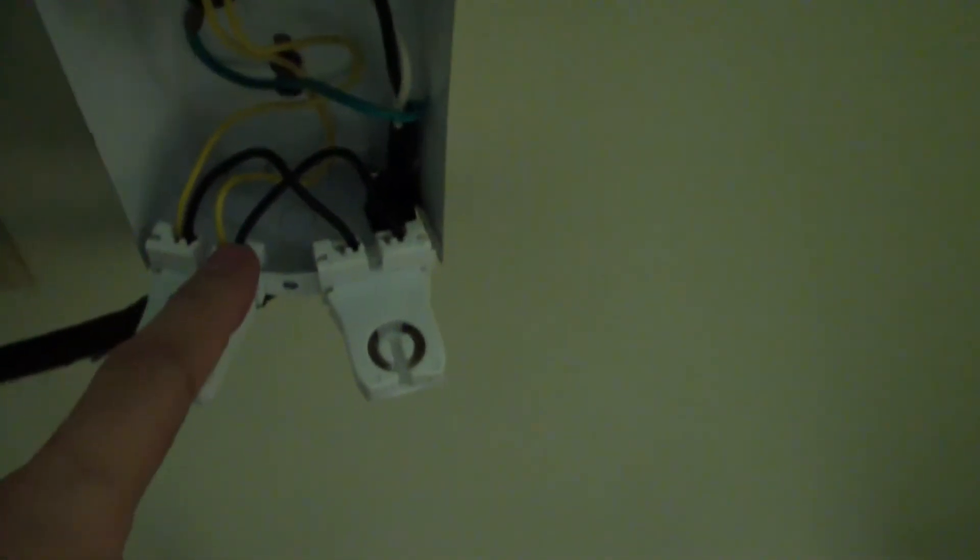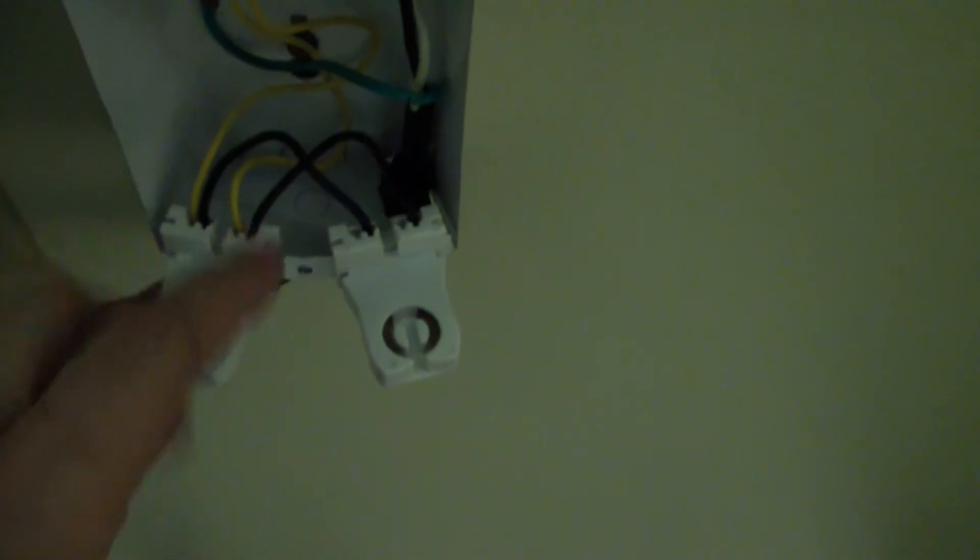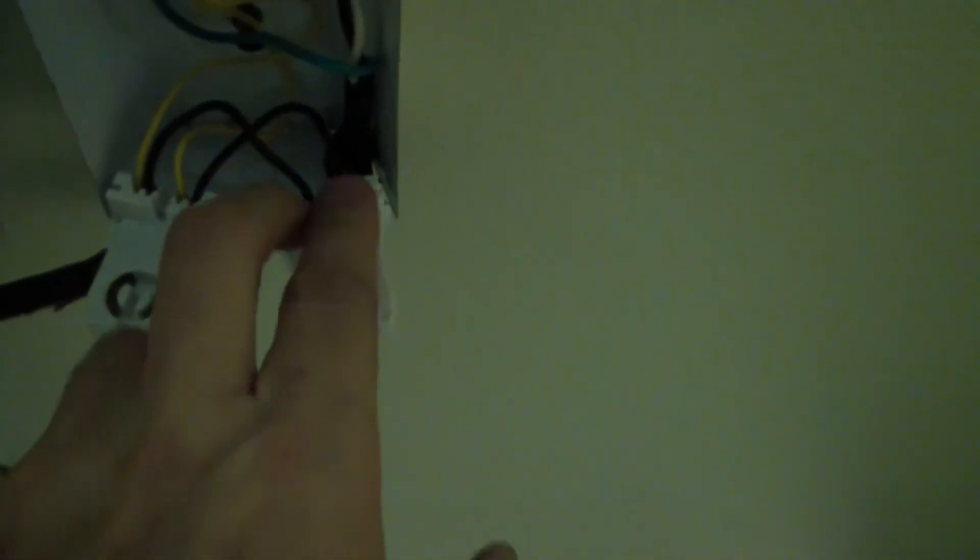Here's the fixture. Let me spend 20 seconds to show you how to rewire it. This big black wire here is the power wire coming in to the fixture. You can see it's got a black and a white wire that are coming in and going to the ballast. We're going to cut this black and white wire off from the ballast. And then on this end of the fixture, our bulbs are fed from one end. You can see there's one yellow wire going here and one yellow wire going to here. And those two are jumping over to where it's repeated. So all you have to do is cut these two yellow wires, cut the black and white wire, wrap one black wire up to one yellow wire, and the white wire up to a yellow wire, and the whole thing will be done. There you go. That took two minutes.